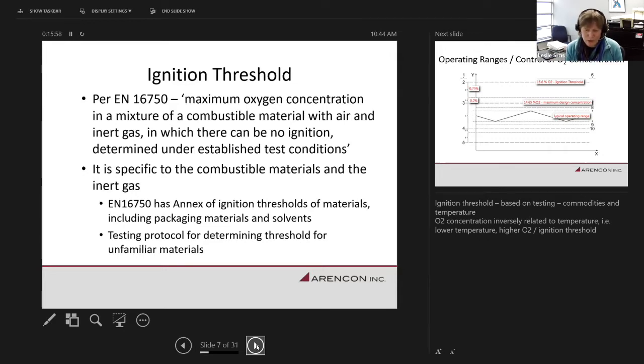If you were looking to alter the ignition threshold, knowing that you've got the cold temperature, you would have to do a test where you've got the temperature at a set temperature, you've got the combustible material, and you've also got the oxygen threshold. So when you're testing for a new material, there's probably a few above the threshold, and then you start to run below. You have to run a minimum of 3 tests to determine the ignition threshold.